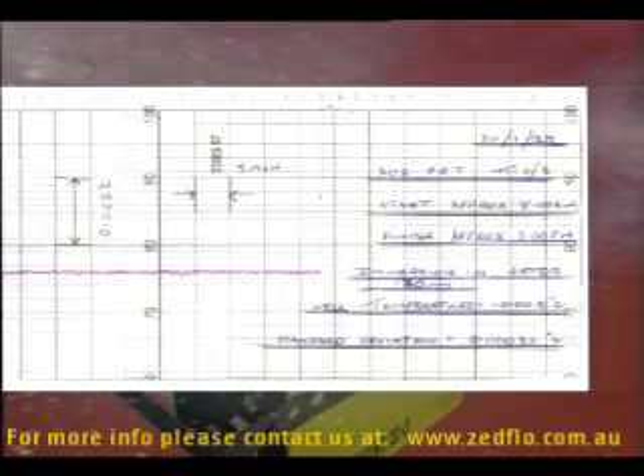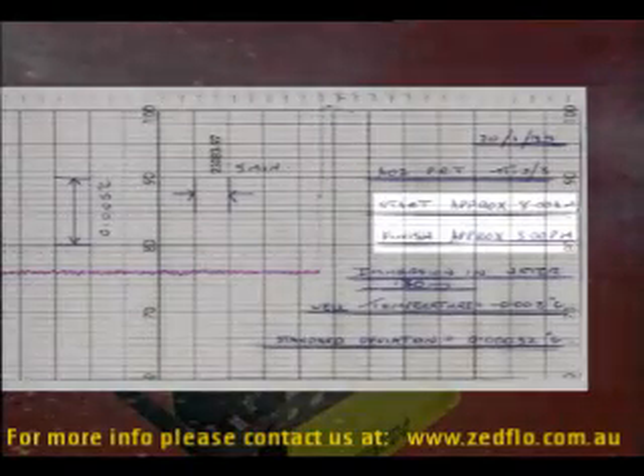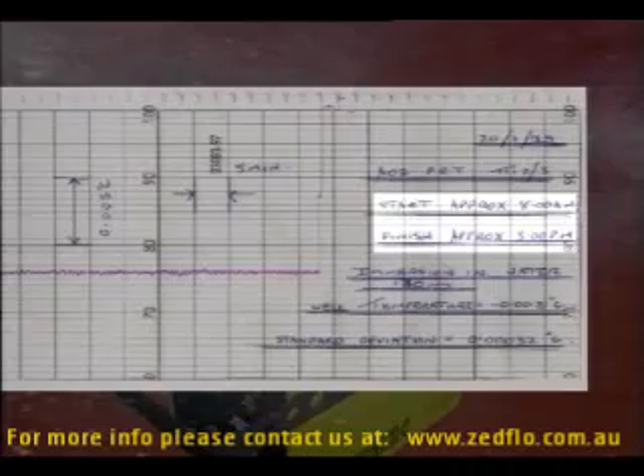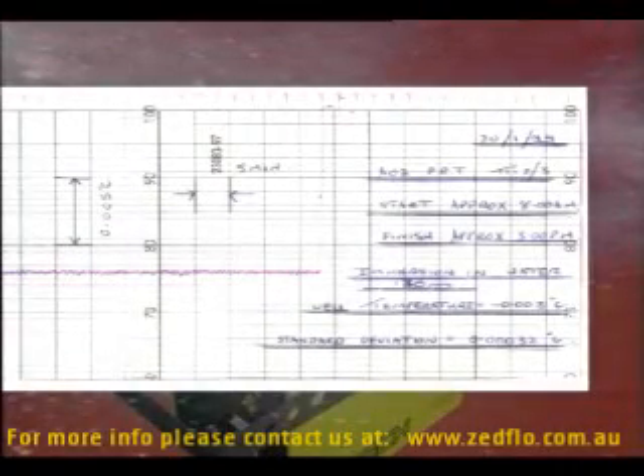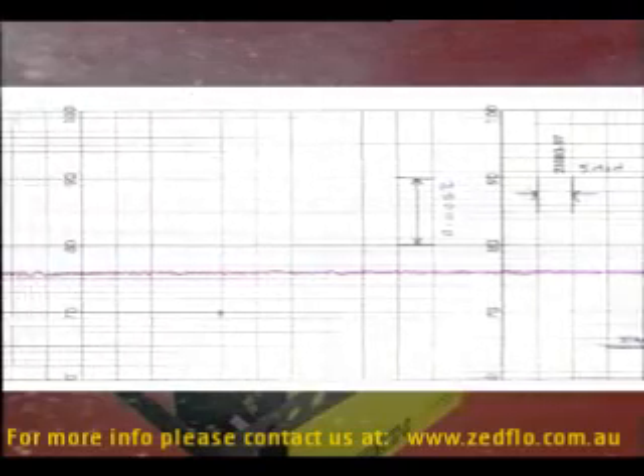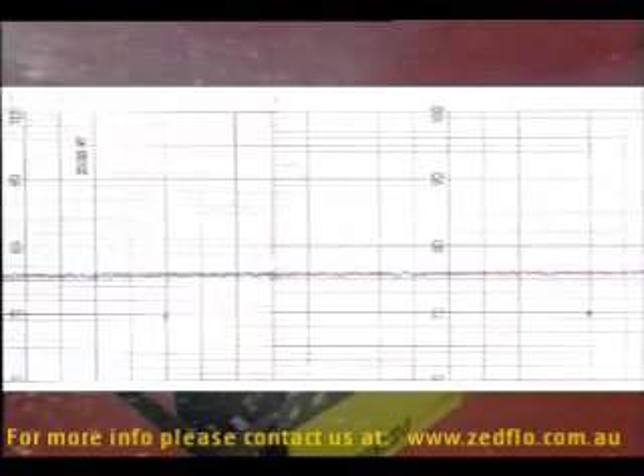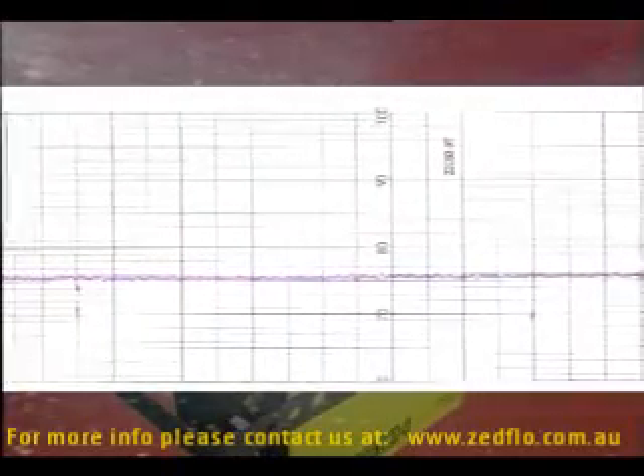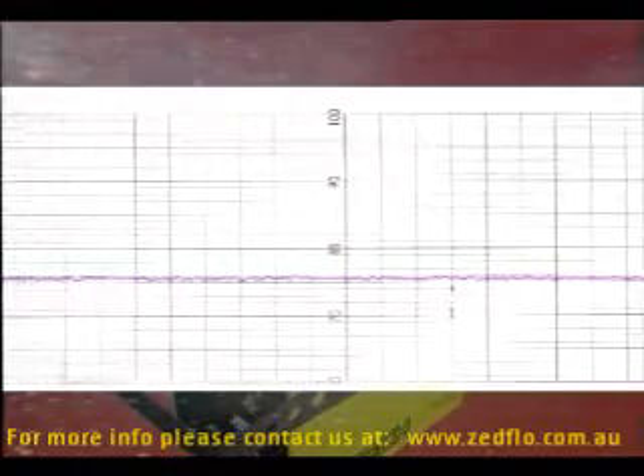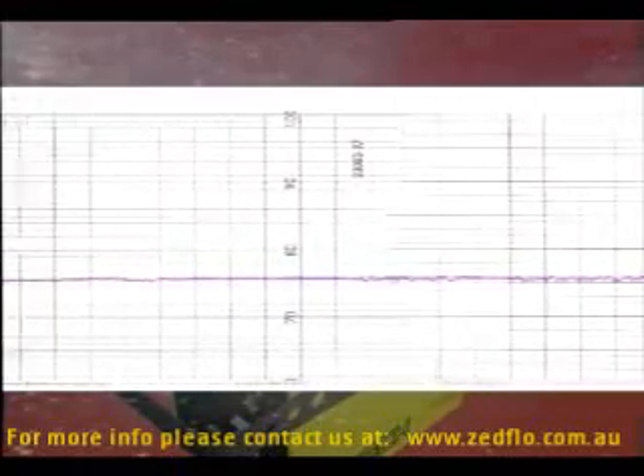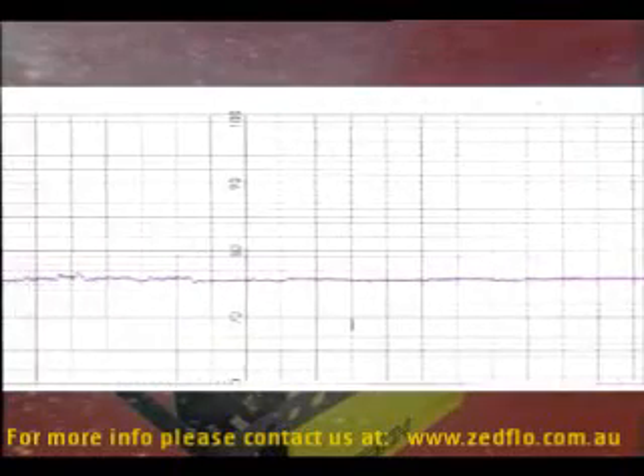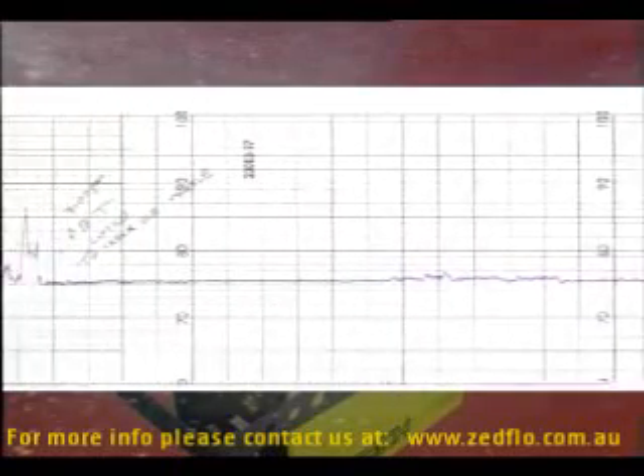This test started at approximately 8 AM and finished at 3 PM. And this is the chart recording of the liquid bath, used as an ice water bath in absolute terms. The temperature was about -3 millikelvins, as we were just using tap water. But the stability over that period was something like a fraction of a tenth of a millikelvin, a very, very stable result over the 7-hour test period.